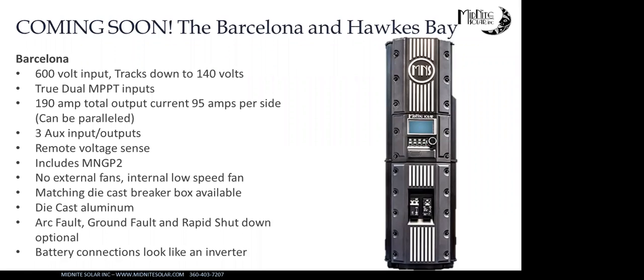It has the same 600 volt input, same tracking down to 140 volts. The difference is it has true dual MPPTs—190 amps total output, 95 amps per side—or they could be paralleled if you had one really large array and wanted to combine it all together.